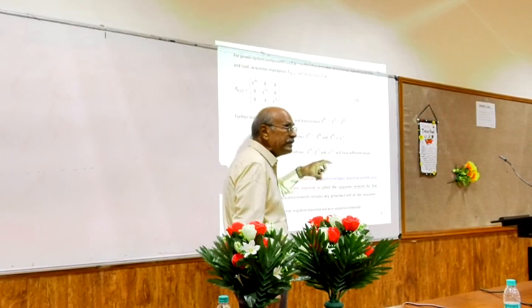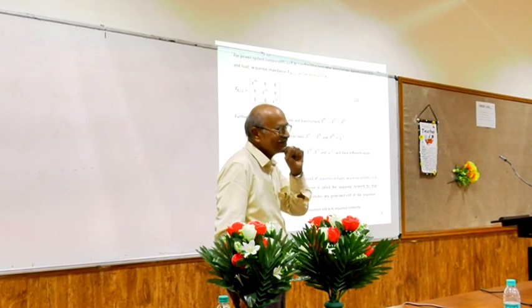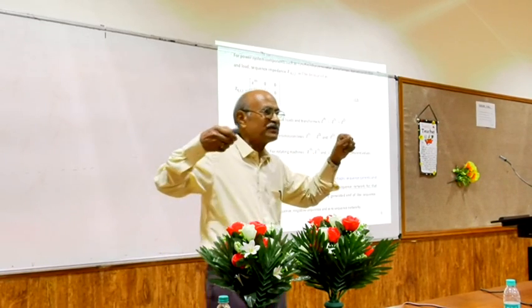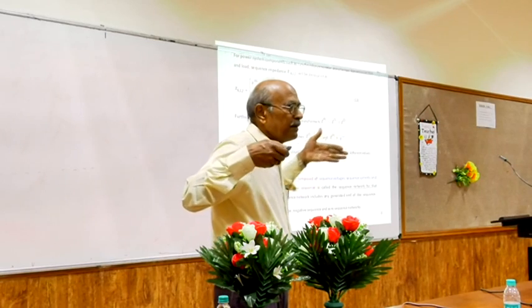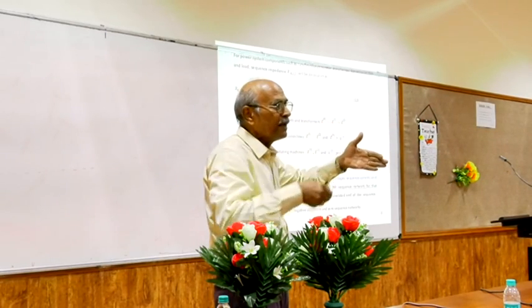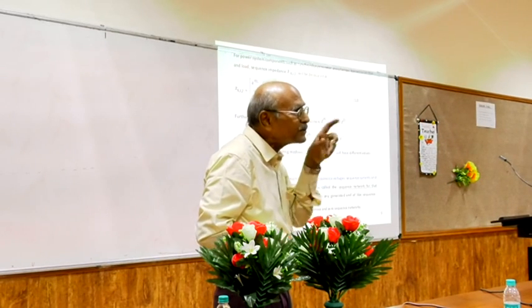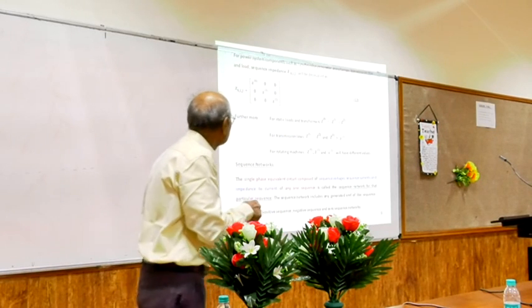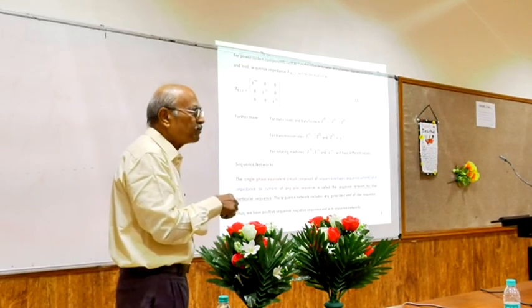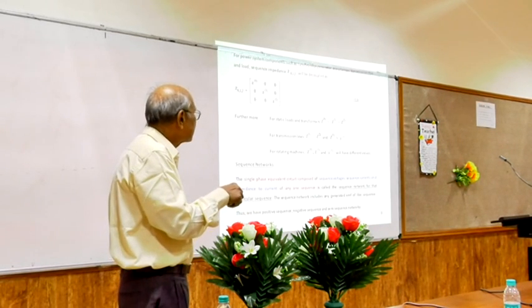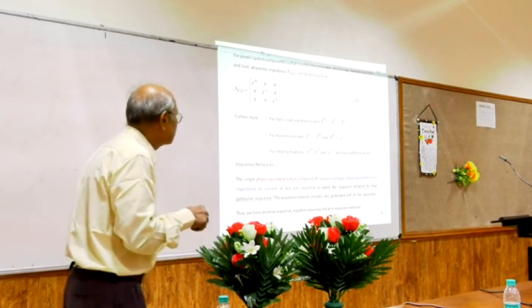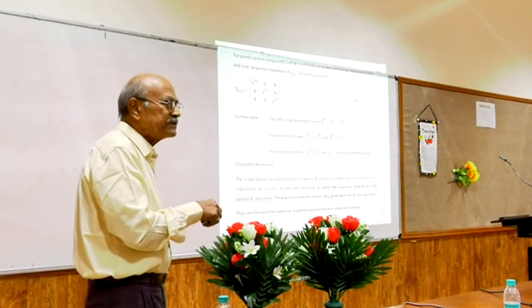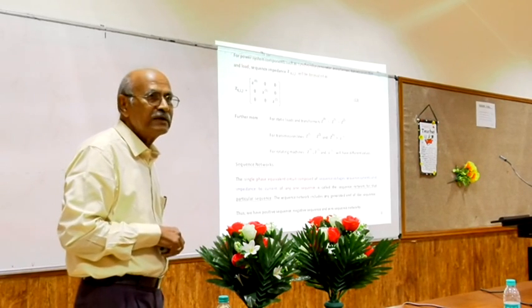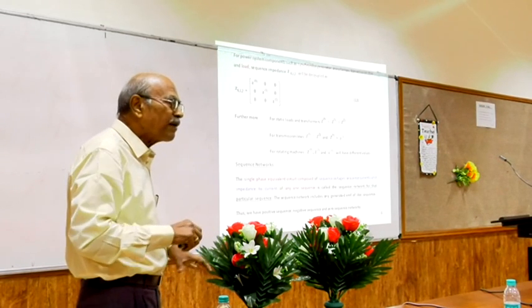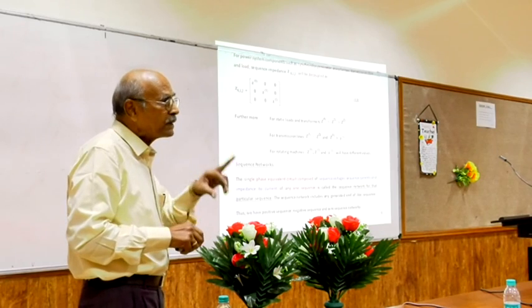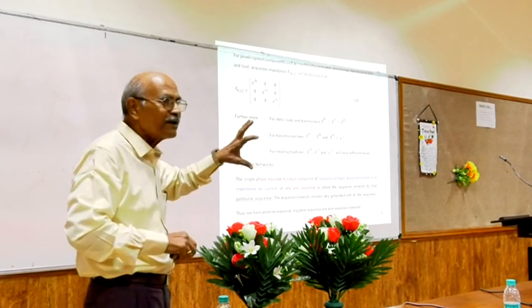Okay, in the ABC frame there will be a mutual term. See, you have A phase winding and B phase winding, and even in the transmission line, A phase, B phase, there is going to be a coupling. That exists only in the ABC frame and not in the sequence frame. Now, if it is a transformer, you can additionally observe that the zero sequence, positive sequence, and negative sequence impedances are equal. For the transmission line, generally the zero sequence impedance is much larger, and positive and negative sequence impedances are equal. For a rotating machine, in general all three will have different values, but not the coupling terms; the off-diagonal terms will be zero.